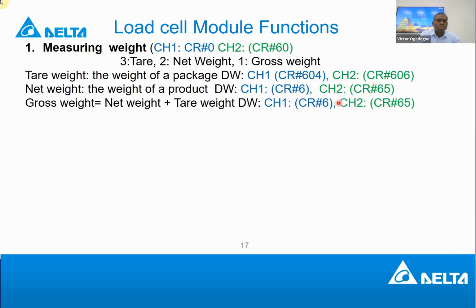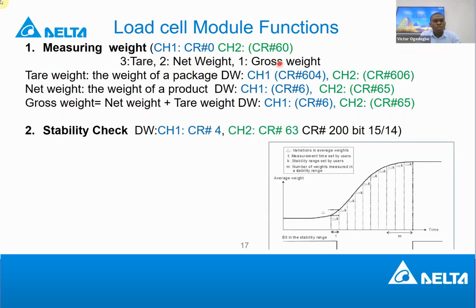And then the last weight is the gross weight. The gross weight is the addition. In your application, you may want to know both weights before you take action, before you write your instruction, your algorithm. So you also get the gross weight from this register. This is the first function. You can measure your weight and you can be so specific on the type of weight that you want. Is it tare weight? Is it net weight? Is it gross weight? Another function is stability check.